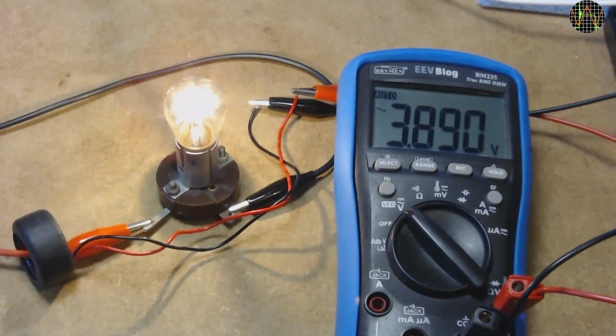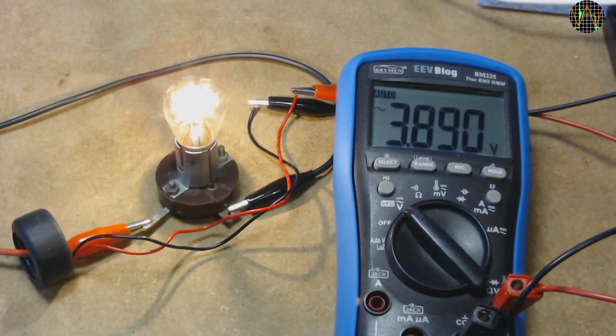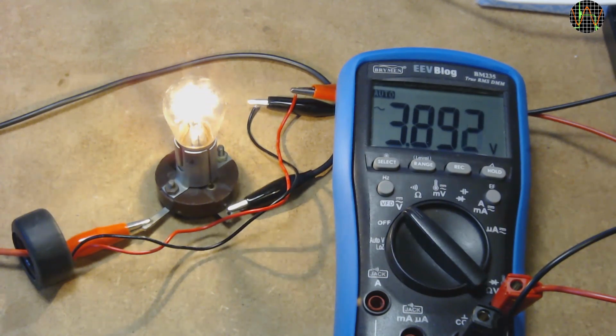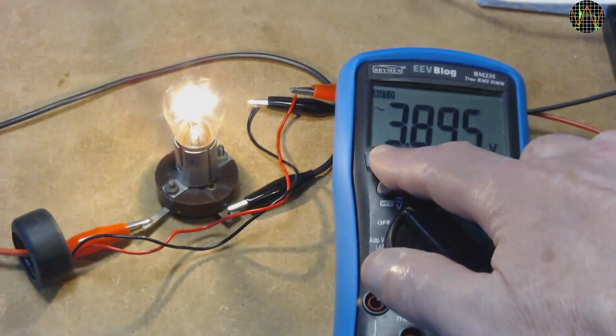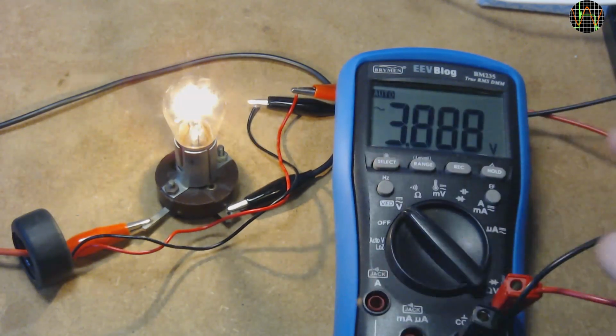The BM235 in normal AC volt mode shows about 3.89 volts in the open coil. Because of the high 10 megohm input resistance of the BM235, almost no current flows and it can be regarded as an open circuit. If I select the low pass filter mode for variable frequency drives, or VFD, the same voltage now reads 16.1 volt. Interesting. And in low Z mode, where the input impedance is reduced, the same voltage reads 7.3 volts. Which are we supposed to believe?